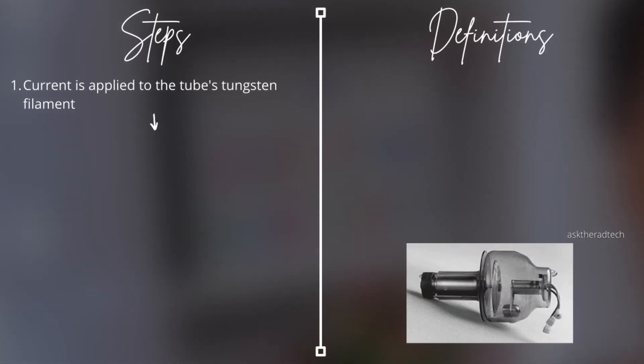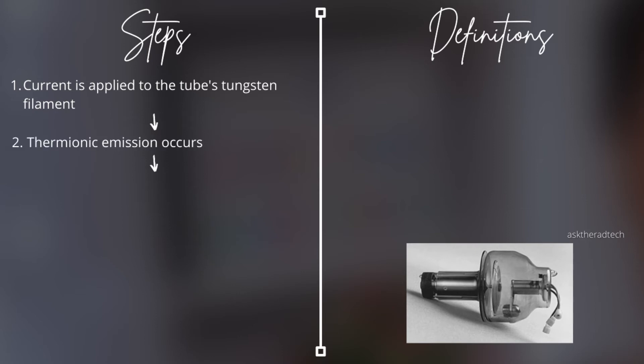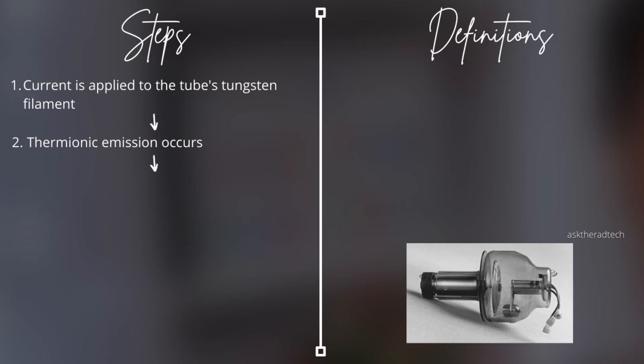Now let's get into the actual steps of x-ray production. Step one: current from the generator is applied to the cathode area and passes through the tungsten filament, heating it up. Step two: as the filament heats up, thermionic emission occurs. Thermionic emission refers to electrons being emitted from a surface — in this case the filament — when heat energy is applied. The word 'thermionic' breaks down into 'thermal' and 'ion,' meaning heat is applied to the metal.